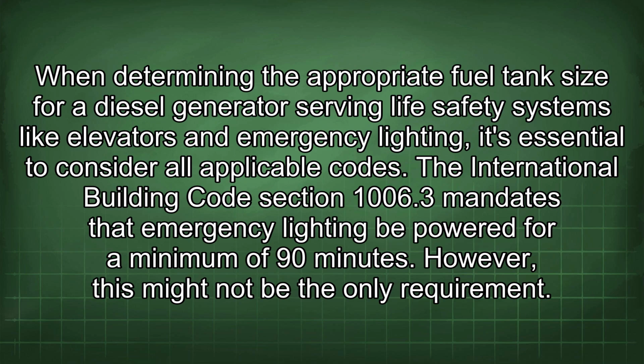When determining the appropriate fuel tank size for a diesel generator serving life safety systems like elevators and emergency lighting, it's essential to consider all applicable codes. The International Building Code Section 1006.3 mandates that emergency lighting be powered for a minimum of 90 minutes. However, this might not be the only requirement.